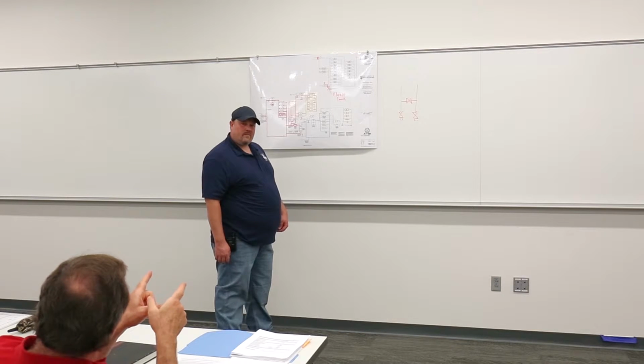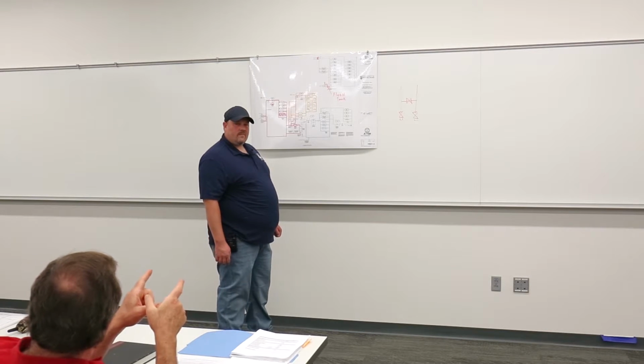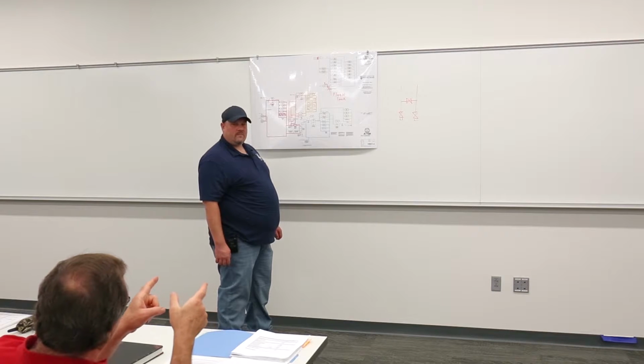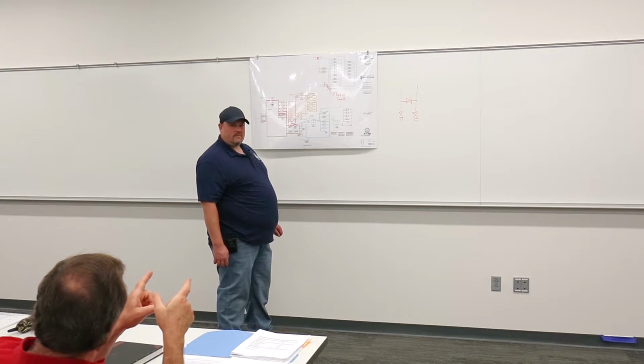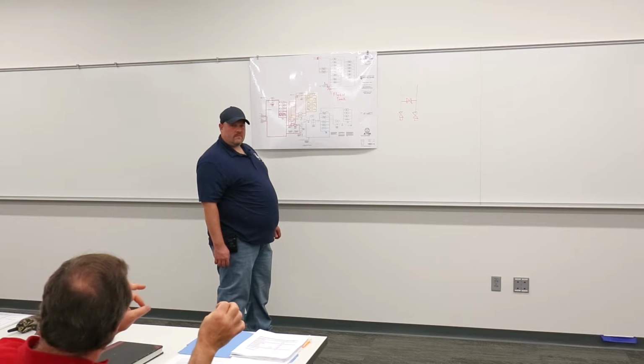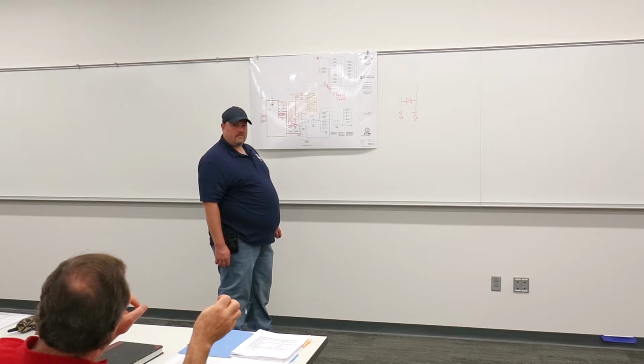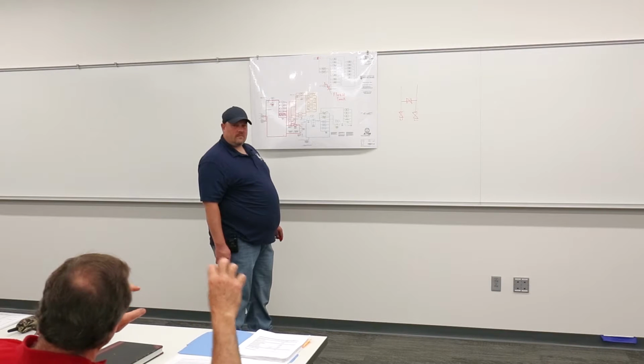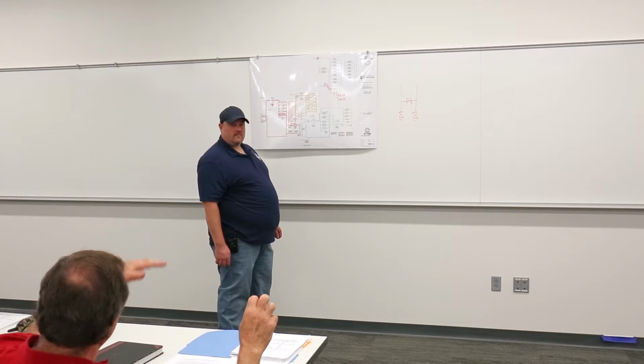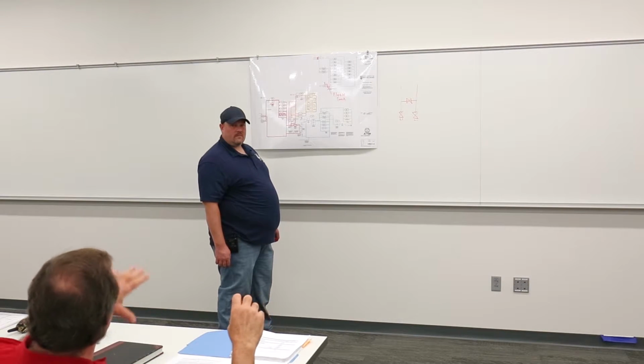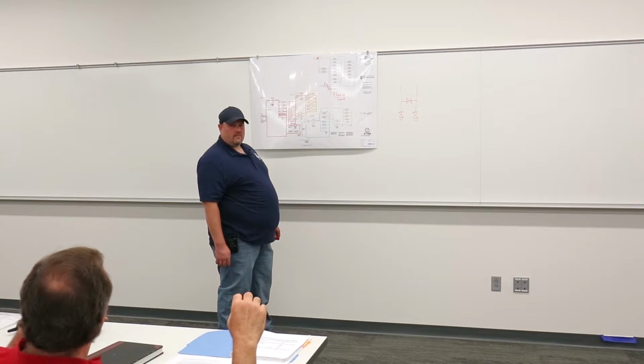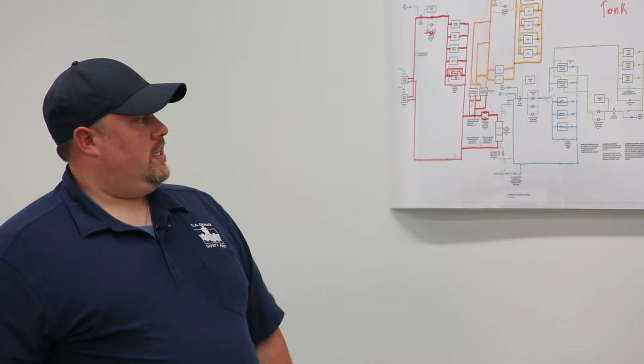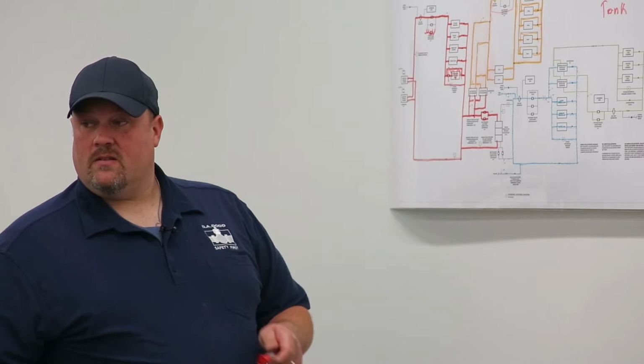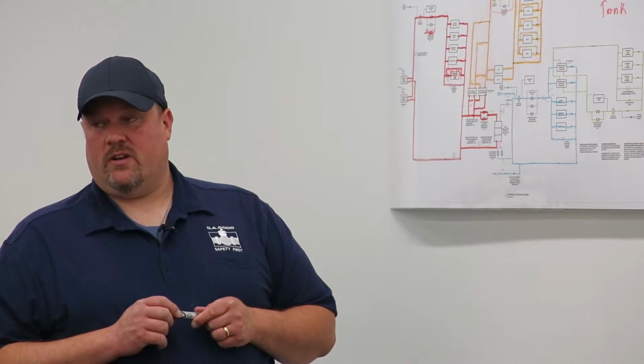Okay, the chilled water, at least when I was working with them on it, does not have an expansion tank because what we do is we only lock down one side. We lock down the return with the return valve. We leave the supply open. So it doesn't circulate through campus, but it gets its expansion and contraction from the campus. It does have an expansion tank. It does? Yes, sir. There is one down there.